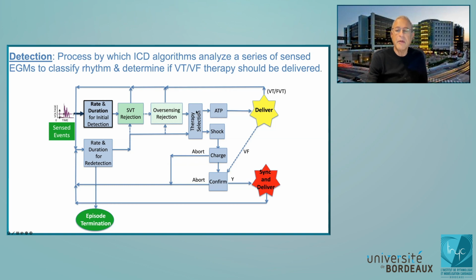And if it's ATP in a transvenous device, this therapy is delivered immediately. If it's a shock in a transvenous, in any device, then we have a charging period, and that can go on for 10 seconds, right? I mean, 10. So the device after that takes a sneak peek. This is called confirmation, and it's often not very precise, but it takes a sneak peek and says, is the rhythm still fast or did it stop? And if it is, it delivers the shock.